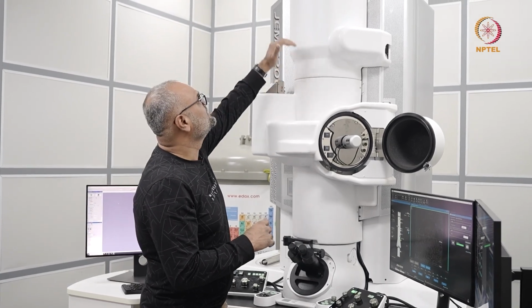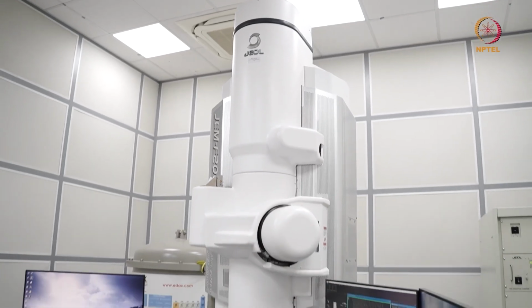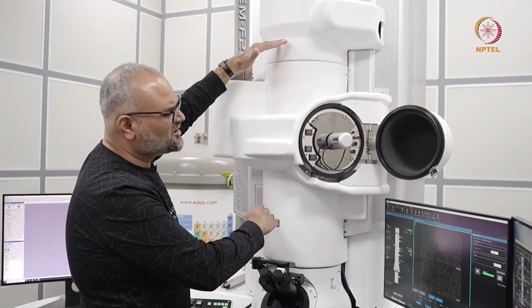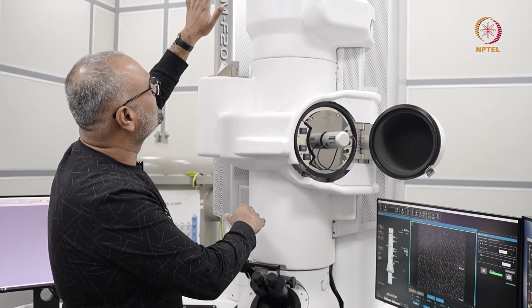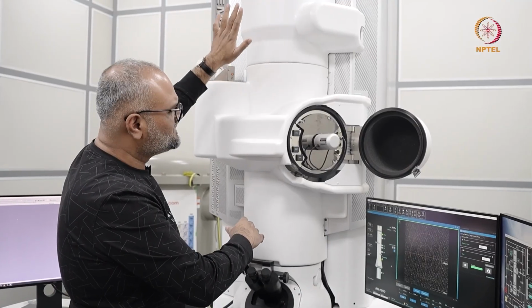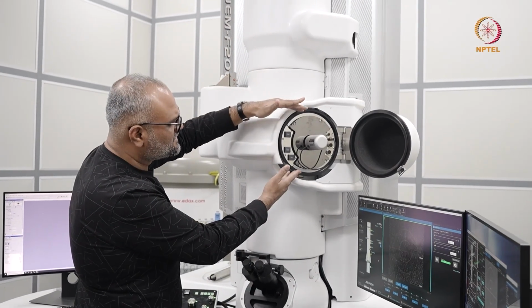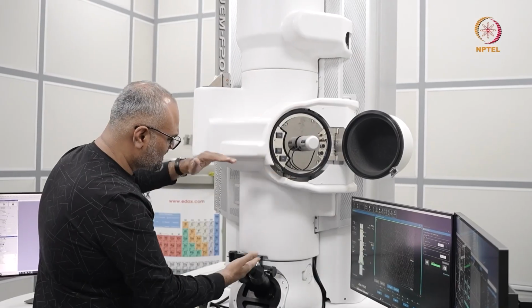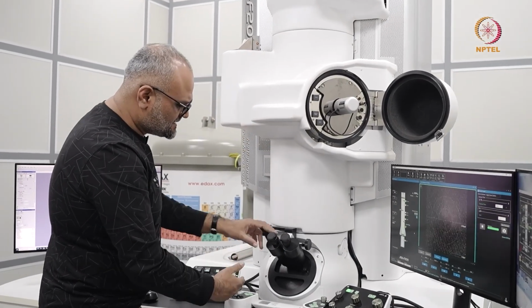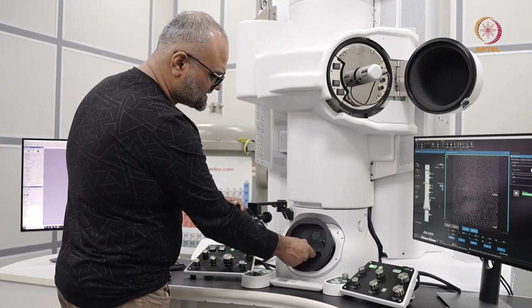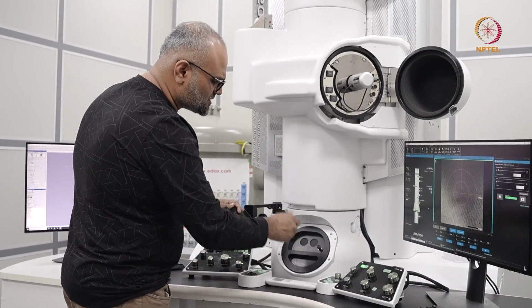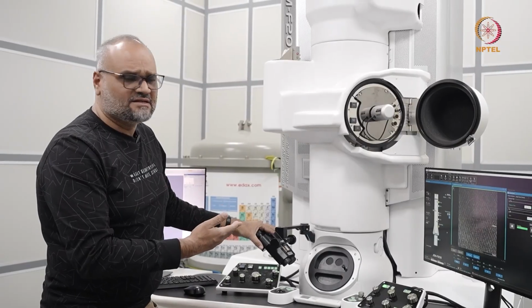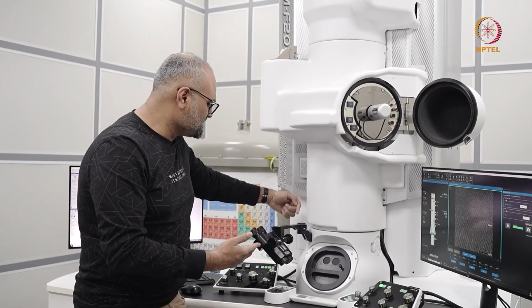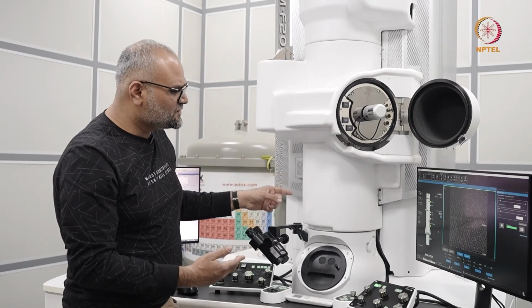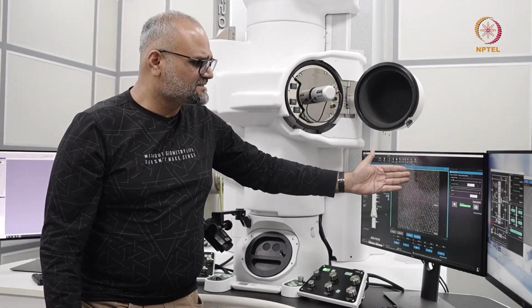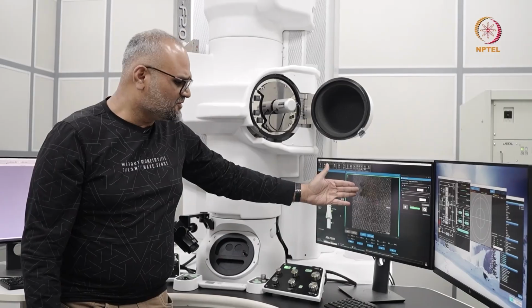So here is where your field emitter is, and this section consists of your condenser lens, the objective lens, and the apertures. In this instrument, all the apertures and everything is concealed, you do not see them. Here is where your specimen holder goes into the microscope. You have the illumination lenses again here, the binoculars and the fluorescent screen over here. Now, this instrument also has a fluorescent screen camera. So you have a camera which is pointing towards the fluorescent screen here, and you can record and see the live images on the fluorescent screen on the microscope computer.